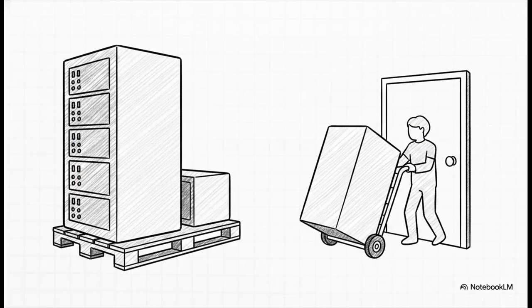Now, if you're a facility manager, seeing a weight of 2,300 kilograms probably makes you sweat a little when you start thinking about logistics and shipping docks. But here's the saving grace from the documentation: the 500 kilowatt model is designed with a modular architecture. What this means is that for transportation, each module maintains a footprint very similar to the 200 kilowatt sidecar. You get comparable packaging dimensions and shipping weights. So even though you're bringing in half a megawatt of cooling power, getting it shipped, transported through your facility doors, and installed remains completely manageable.